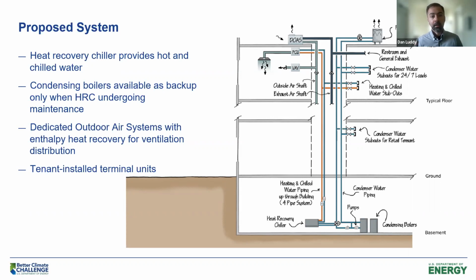As I mentioned, there are dedicated outdoor air systems that provide the tempered ventilation air to all the floors. That operates separately. And then when future tenants come in, they can add their own terminal units to the hot water and chilled water loops. They can put in fan coils. They can put in more efficient options like chilled beams, active chilled beams, to condition their space. And I'll also point out that the owner, as a belt and suspenders backup to this whole system, elected to put in gas-fired condensing boilers to back up the air to water heat pump. Those boilers are meant to run only when the system may be down for maintenance. If it's down for maintenance for an extended period of time, those boilers can turn on and provide a backup.